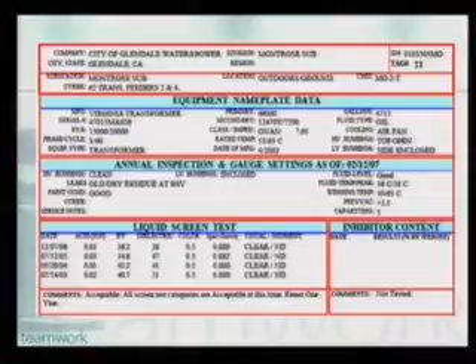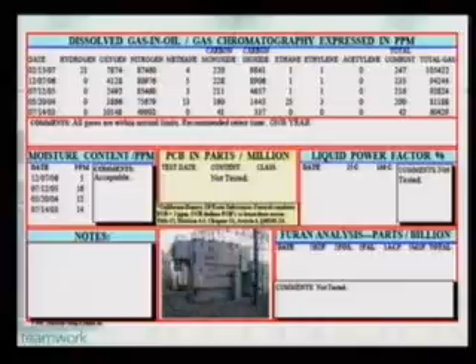So this first part is really a visual, including the oil. They take a clear look at the sample that they take from the oil and see whether or not there's discoloration, as an indication of there might be some contamination or overheating. Most important part of here is a recommendation if they find anything that's out of the ordinary. And then the bottom portion, this is where we spend a lot of time, try to focus on. This tells us pretty much everything we need to know about the transformer. They perform a test called gas chromatography, which analyzes the oil for combustible contents as well as byproducts of overheating. I'll give you some more examples of that. What we look for here is the volume of the different gases that get formed in the oil and any sudden change that would tell us that something has gone awry with the transformer.